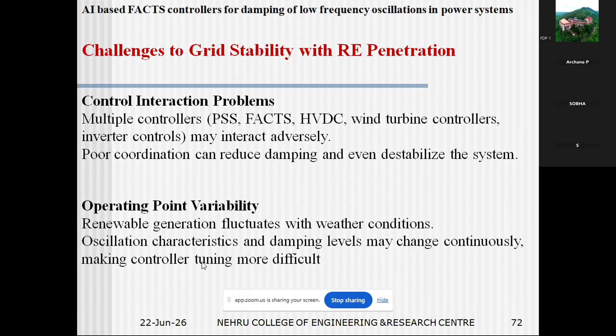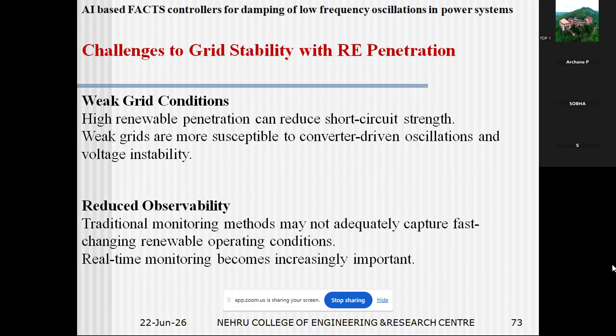Then weak grid conditions. This is yet another area which has to be stressed. High renewable penetration can reduce the short circuit strength, which means the grid has become weak. A weaker grid has more tendency to lose its synchronous torque as well as its damping torque. So converter-driven oscillations and voltage instability can happen. Reduced observability: traditional monitoring methods will become inadequate. Real-time monitoring becomes more important. For all this, you have to have some AI techniques, then only can you address this.